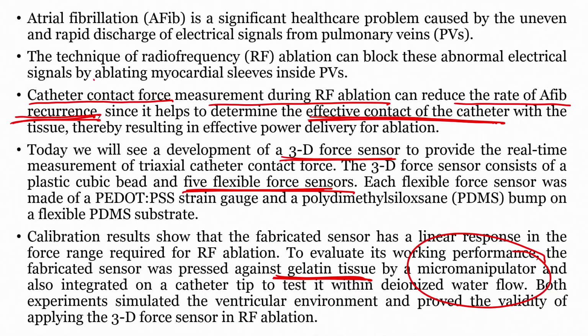That effect of blood we have to subtract from the actual force data that we are measuring. So, we performed the catheter contact force experiment and measured in water to understand the effect. Both experiments simulated the ventricular environment and provided validity for applying the 3D contact force sensor in RF ablation.